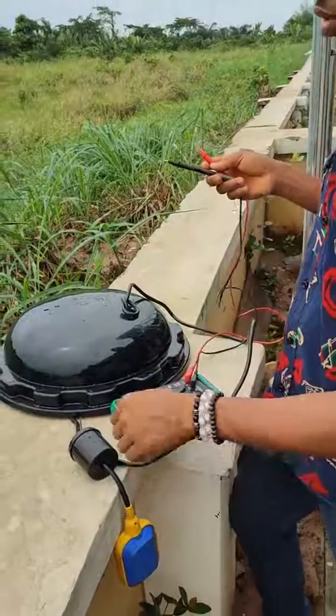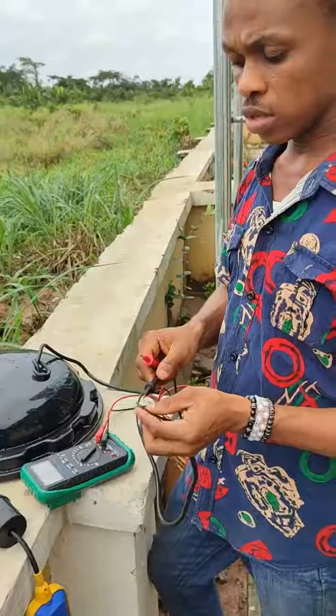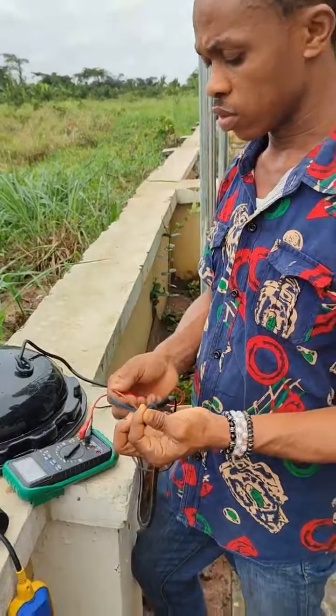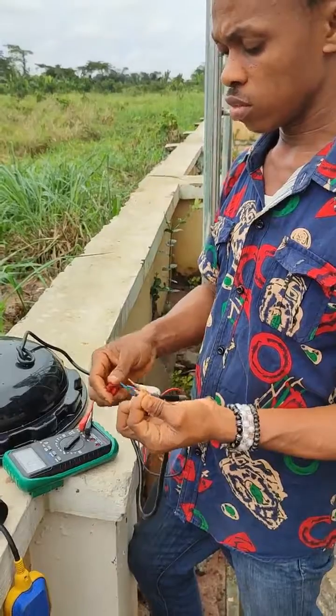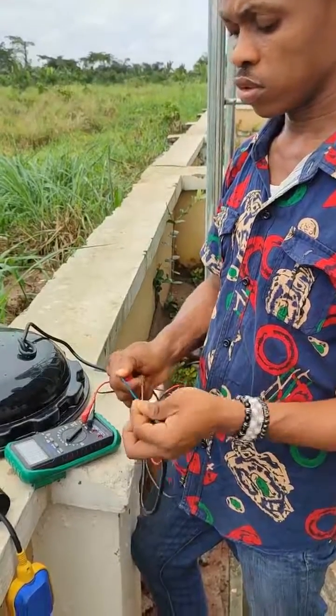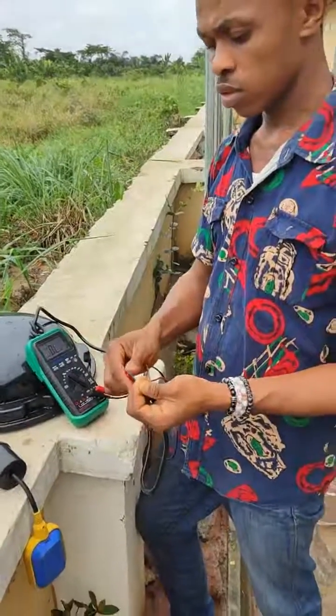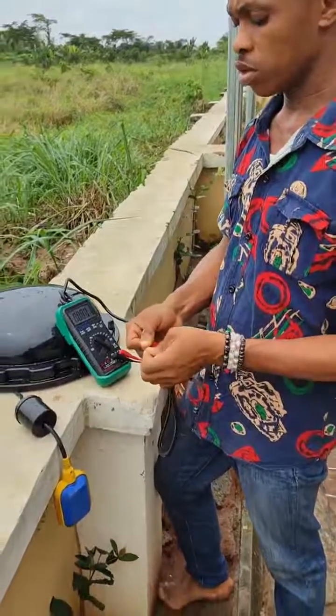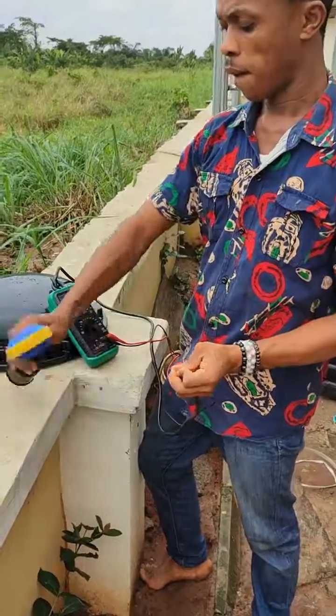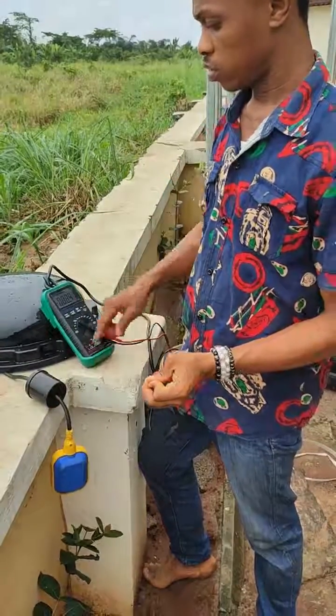Let's check which of these wires is normally open and which is normally closed. You can hear the sound — this one is normally open, this one is normally closed. When the float rises, the sound stops and the resistance rises, confirming the switch has opened.